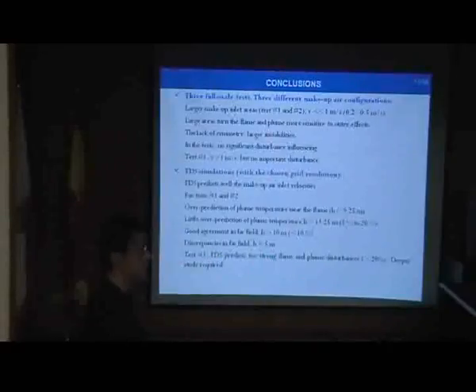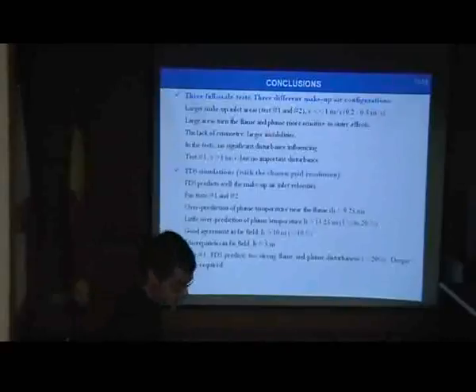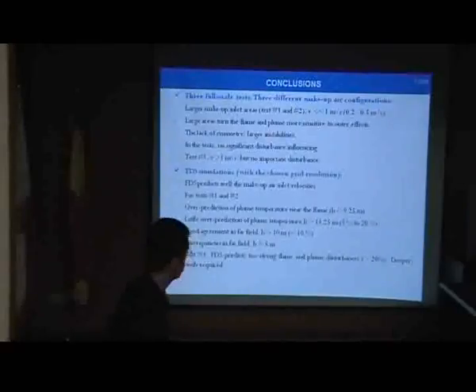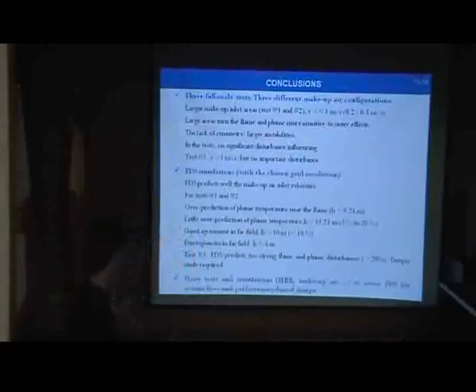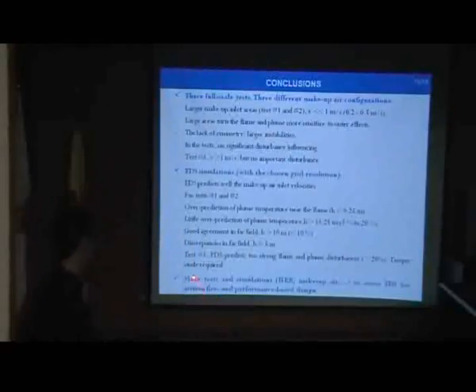And, well, as you have seen, the thermal field becomes homogeneous, and there is no thermal stratification, so we can say that it is not physical. Although, a different study is required to draw further conclusions. And finally, taking into account the two first conclusions, it's clear the necessity of performing more tests and simulations to assess the stability of FDS for this kind of analysis.